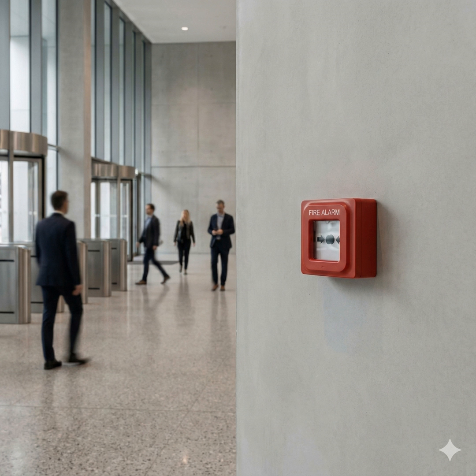The system isn't an island. It's an integrated platform that has to communicate flawlessly with the building automation platform, the BMS, and all the other infrastructure. So if that fire alarm system fails to transmit the necessary signal, maybe because of a fault, power loss, or even a data collision, those vital smoke control sequences just don't happen. And the building's risk profile changes instantly. It just emphasizes why the system's performance relies entirely on meticulous design and, just as importantly, unwavering maintenance throughout its entire operational life.